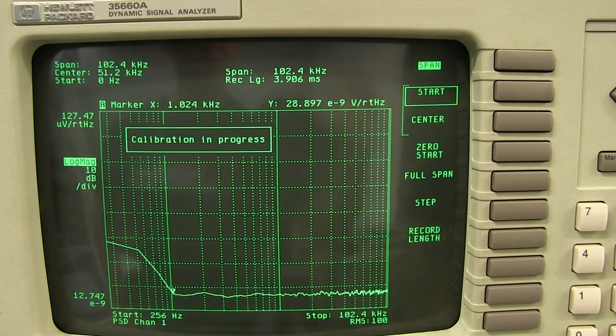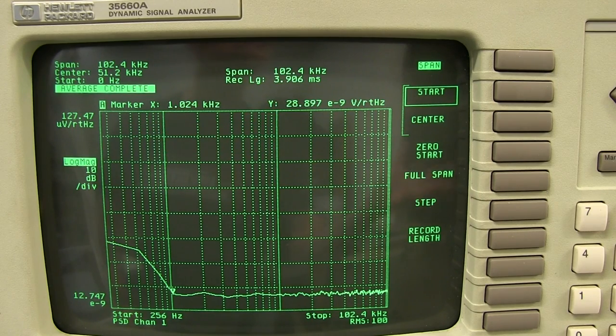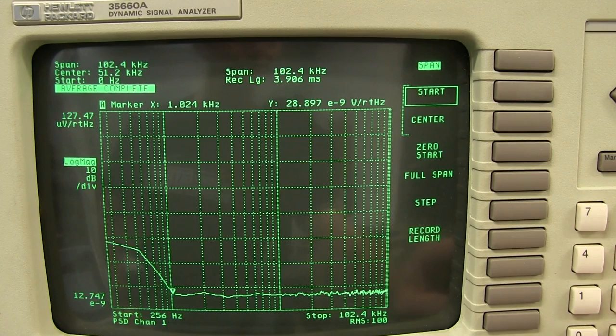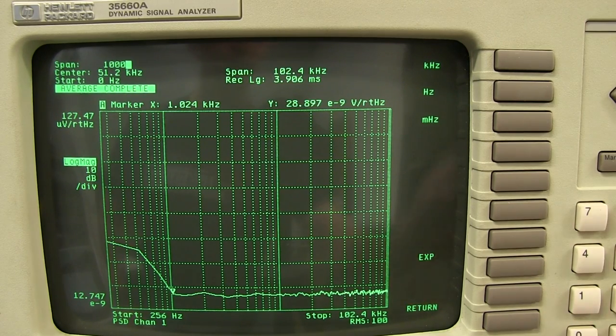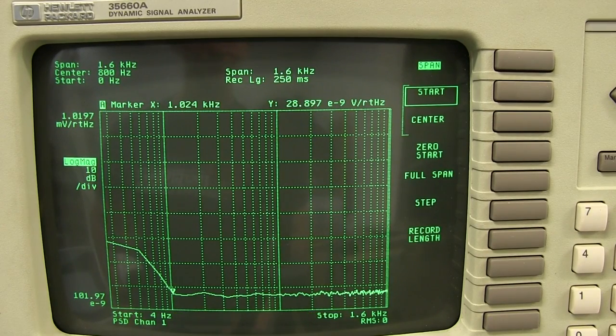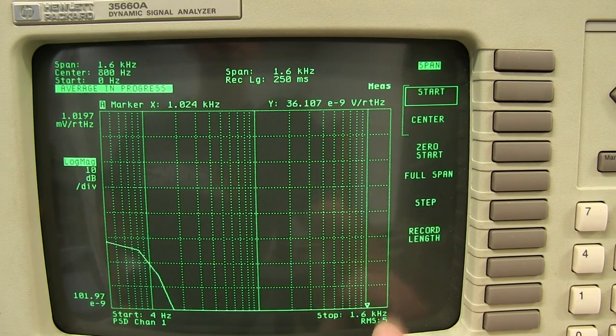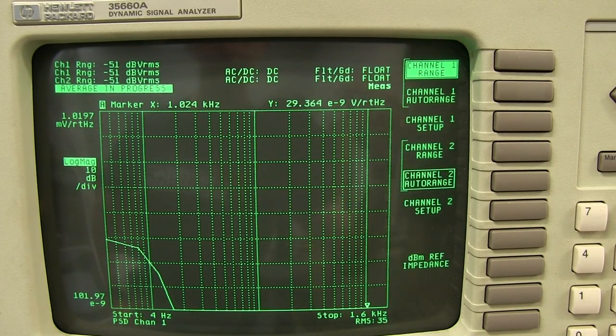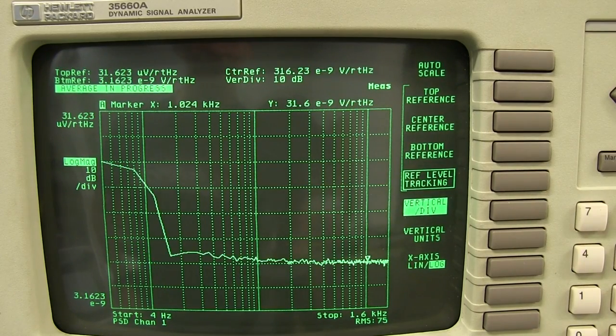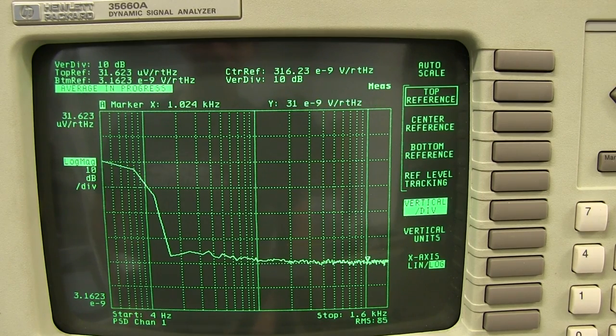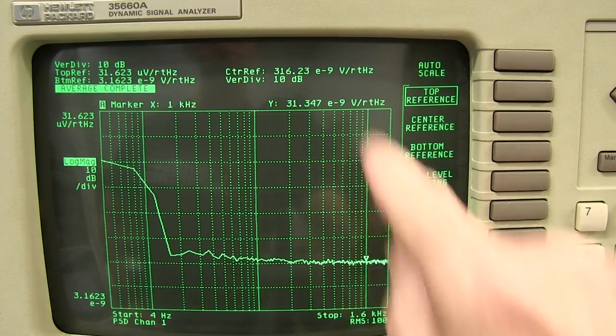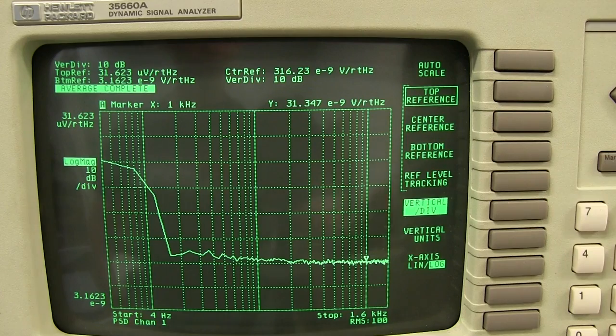You just press the frequency button on the front. You can see these DSAs are specifically designed and optimized for these types of measurements. We can go to span, press the span button, and type in 1000 Hz — a kilohertz range — and then it's going to restart. You can see it's automatically restarted and will do the RMS averages. It takes longer of course because it's lower frequency, so it takes a quarter of a second per record length. We press Scale and auto-scale. And look at that! We can now put the cursor at 1 kHz. We're getting a value of about 31 nanovolts per root hertz — that's the noise floor of this thing. Not very spectacular.